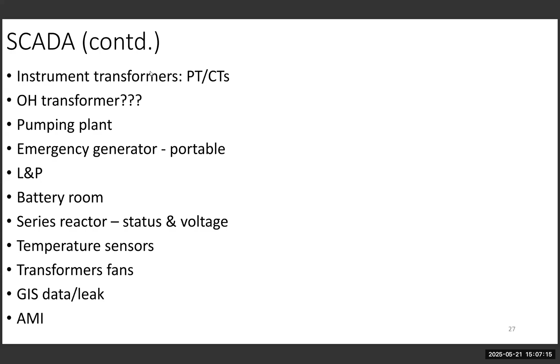Sometimes intelligence is knowing if equipment drops. I'll give you an example and then move on. If you've ever been to a substation, you'll see that transformers have a lot of fans, and depending on how hot it gets, those fans run more. Sometimes there's 3 sets of fans, and after a certain temperature they kick in. You'll be surprised how much the system will be derated, or the capacity lost, if those fans are not working.